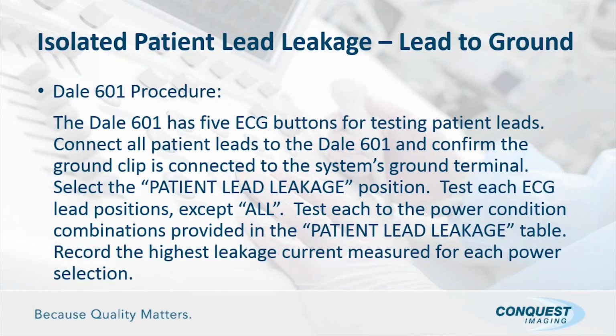Select the patient lead leakage. That's the position on the Dale 601. And you test each ECG lead. The requirement is you don't have to test all. I do, as a general rule, test all, but NFPA does not have any requirement to test all. In fact, they say exclude it. Test each to the power condition combinations provided, which is on, off, normal, reversed, open, closed, and record the highest leakage current measured for each power selection. So again, as you change these to the different conditions, you'll see significantly different results.